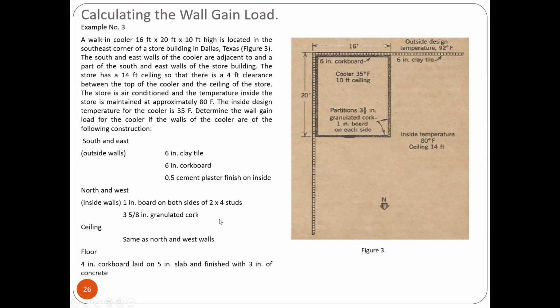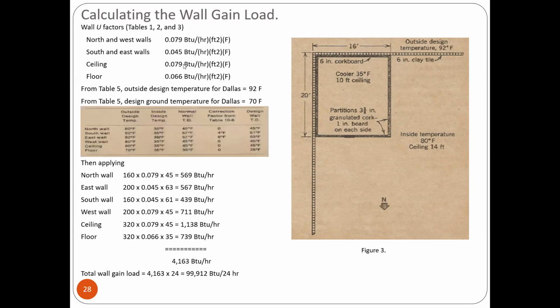So insulation kinuha. So from table 5, outside design temperature 92 Fahrenheit, design ground temperature 70 Fahrenheit kasi meron tayong floor. When applying, so 160 times 0.079 times 45 is 569 BTU per hour. East wall is 200 times 0.045 times 63 equals 567. South wall is 439. West wall is 711. Ceiling is 1138. Floor is 739. And total is 4,163 BTU per hour. For 24 hours, this is 99,912 BTU per hour, 24 hours.